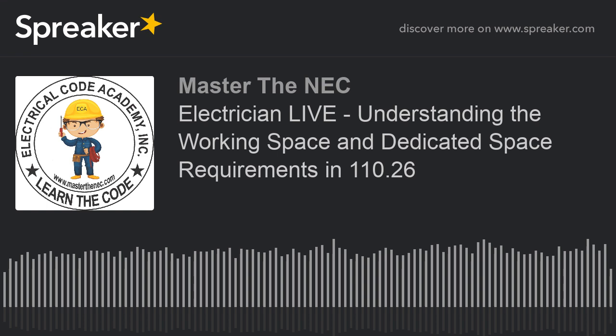I've got a switchgear room. I've got the switchgear in place, and I've got a door opposite, facing the equipment. Not on the sides, but opposite. Okay. Well, if I've got the working space, and I followed everything I needed to do in 110.26A, everything's good. I've got my working space, and I can literally walk straight out of that working space right out the door with no obstruction. If I've got a post in the middle or some kind of column in the middle, that's not unobstructed. Okay? I think you're saying, well, common sense, Paul says I can go around it. Hey, if the room is dark or something goes on or it's smoke filled and you might not see the opening, it says clearly continuous and unobstructed.